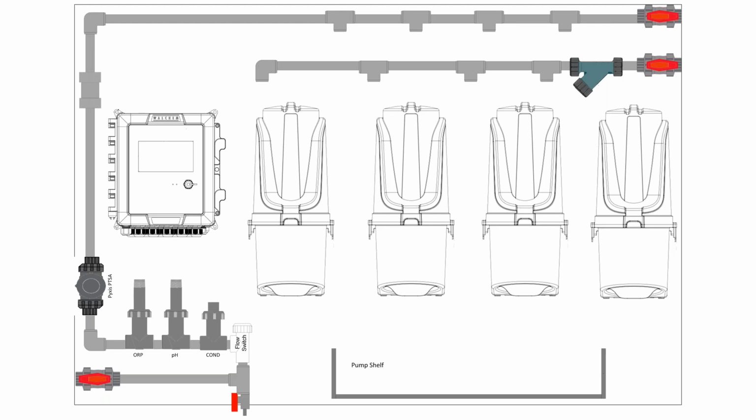So loss of feed, loss of control. The discs themselves can be utilized as supplemental, manual dosing as well. They dissolve rapidly. So little tricks like that help you expedite transition. And if you happen to be transitioning from liquids to solids, it's fairly seamless to do that transition because you're able to get the solid chemistry system going, work down the liquids, and then transition over.